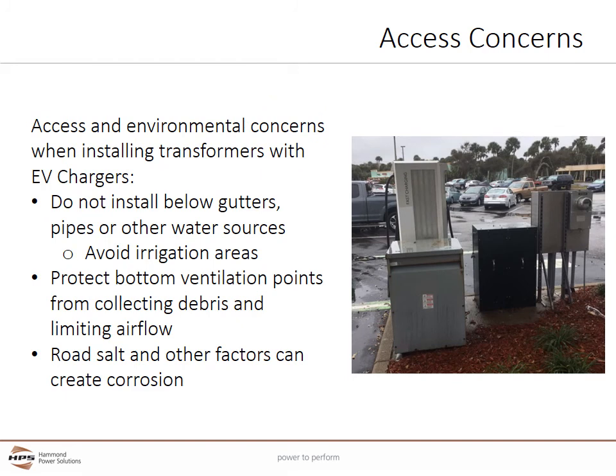Additional concerns include: do not install the transformer below gutters, pipes, or other water sources which can cause directed flows of water on the transformer. This would include areas which may have water irrigation, such as lawns. Protect the bottom ventilation points from collecting debris such as garbage or leaves that would limit airflow. Road salt and other factors can create corrosion. Stainless steel is an option and can be more aesthetically pleasing. Custom enclosure colors are also available.